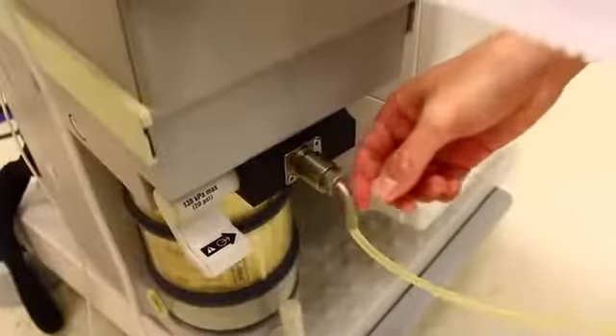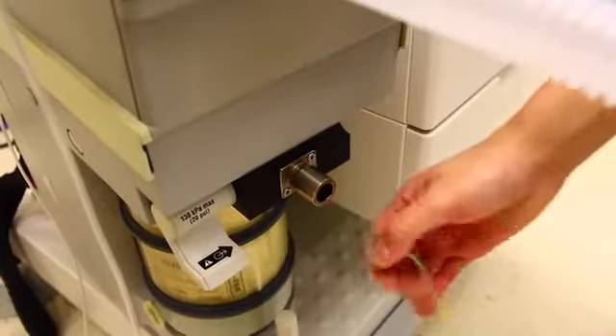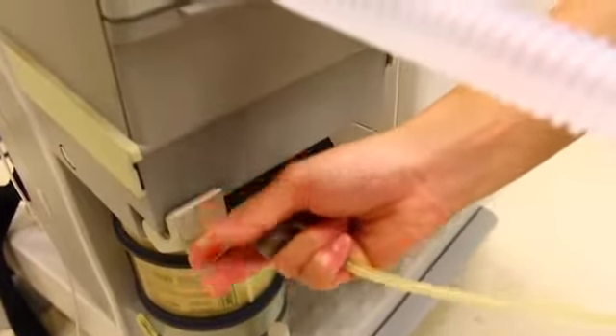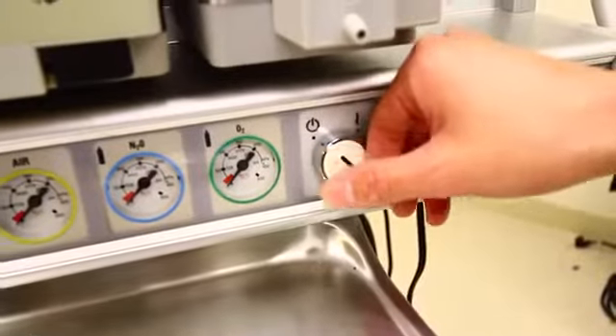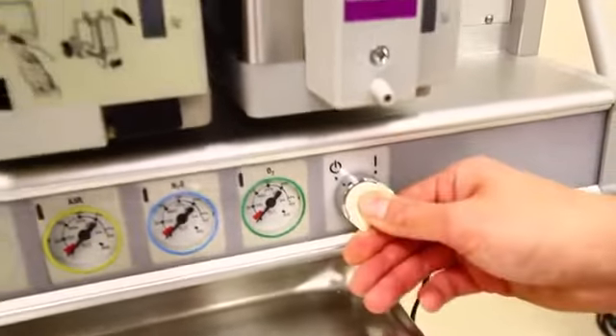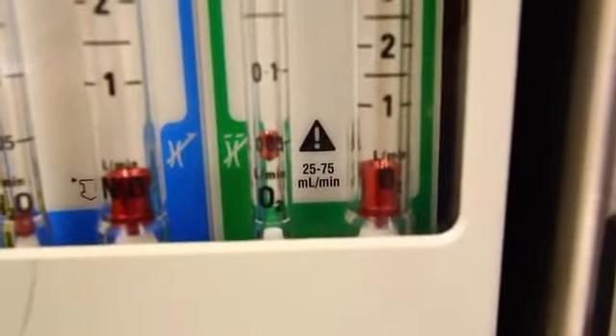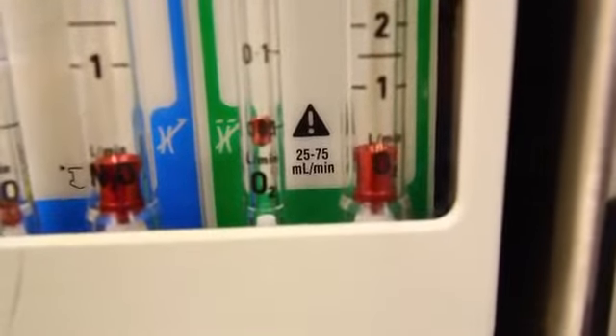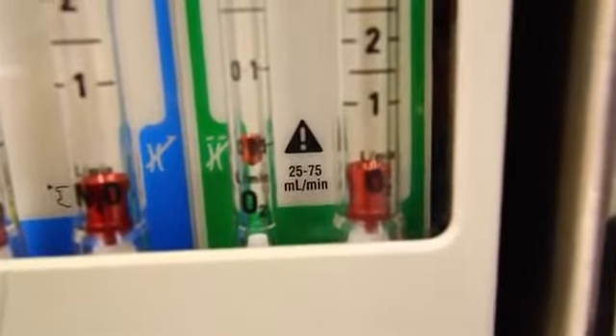Make sure to close each vaporizer when you're done. Next, you want to remove the suction bulb and close the common fresh gas outlet switch. Now turn the machine master switch to the on position. After turning on the machine, the oxygen float will rise to a minimum flow of 50 mL per minute.